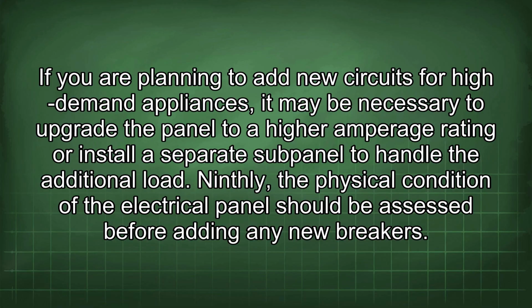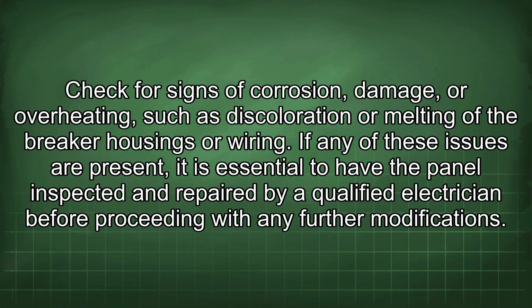Ninthly, the physical condition of the electrical panel should be assessed before adding any new breakers. Check for signs of corrosion, damage, or overheating, such as discoloration or melting of the breaker housings or wiring. If any of these issues are present, it is essential to have the panel inspected and repaired by a qualified electrician before proceeding with any further modifications.